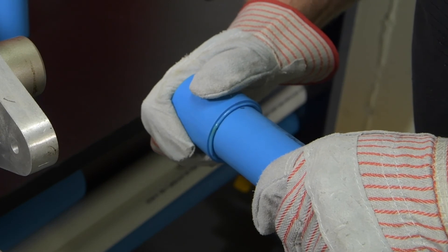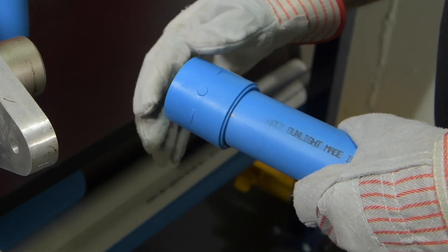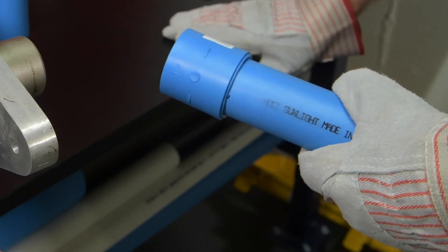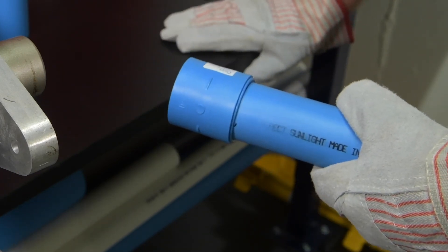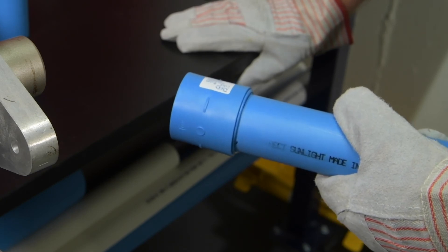Once inserted, hold the joint under slight pressure for 15 seconds to ensure the surfaces fuse. Do not twist the pipe onto the socket and do not over-insert. Check to see the axial alignment is being maintained and adjust only as necessary.